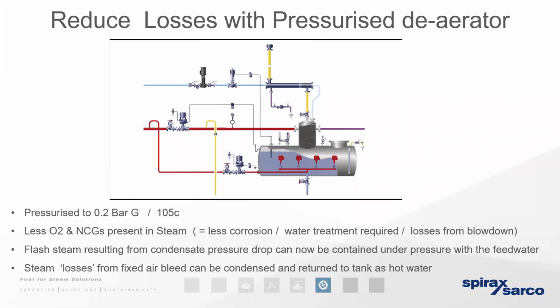But point seven, that's quite often overlooked, it means that by elevating the water to a higher pressure, we can now contain a significant amount of those flash steam losses. We're simply bringing them away from the vents and back to the pressurized deaerator. We can now control and utilize those flash steam losses, and that really helps us to move towards a net zero loss system.